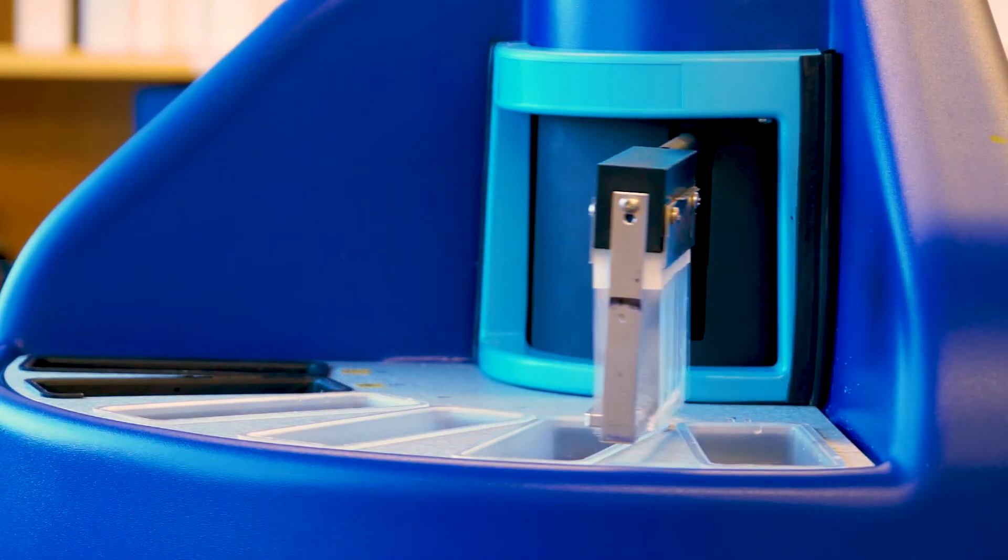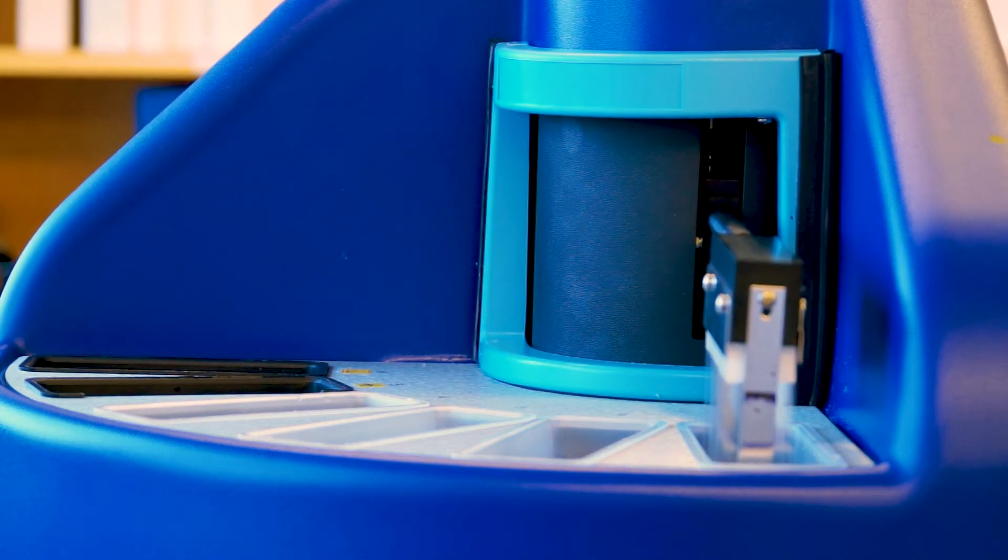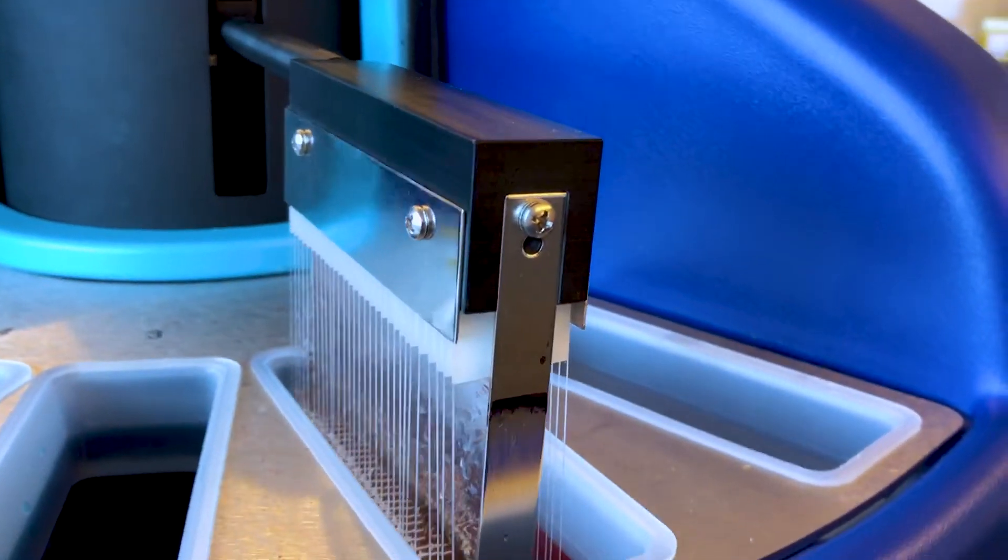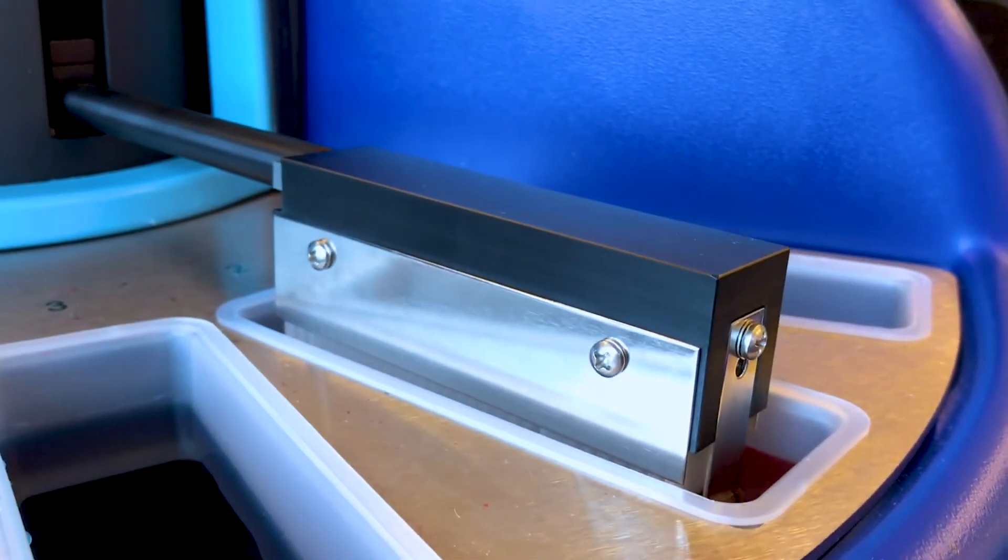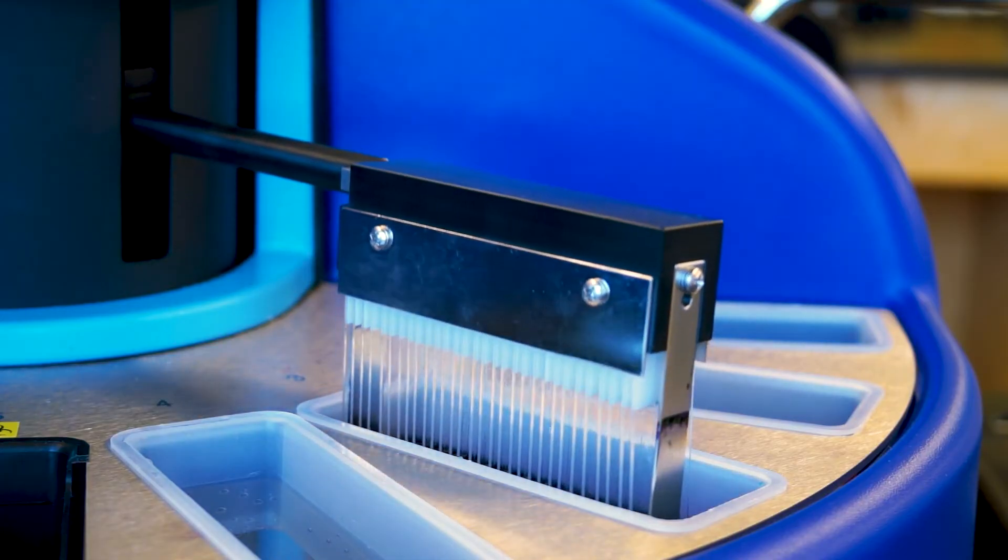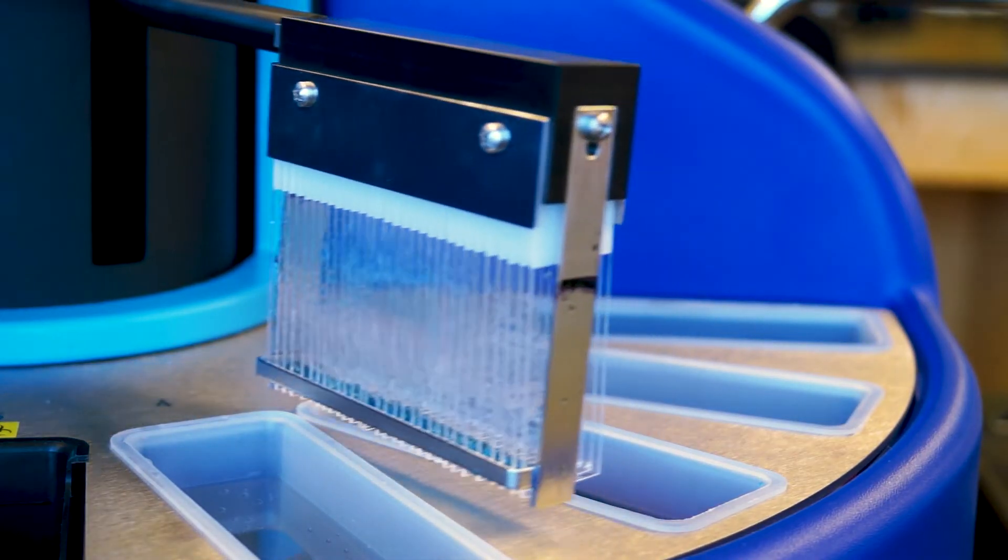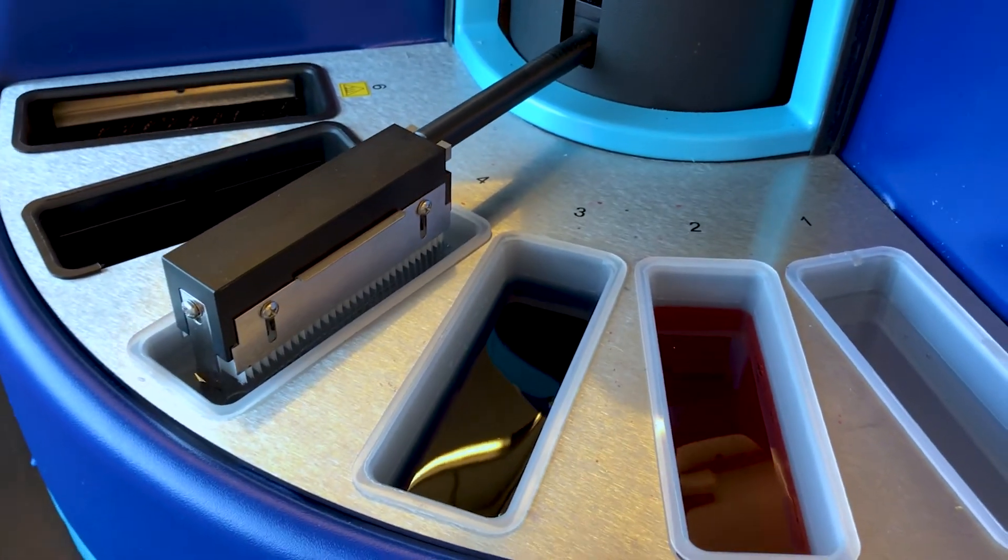The Midas 3 Plus uses the dipped slide technique which is comparable to manual staining. This technique is more familiar to lab technicians and affords more uniform staining without the hassle and uncertainty associated with disassembling and cleaning clogged hoses and nozzles.